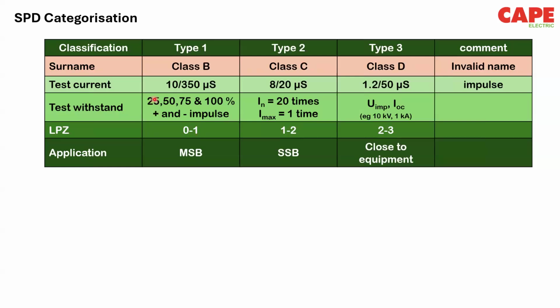Now, how are SPDs categorized? So, as Gopakumar sir said, there are class B, C, and D, the old names. Right now, it is 1, 2, and 3. Type 1 is tested for 10 by 350. Type 2 is tested for 8 by 20 surge current. And type 3 is tested for a 1.2 by 50 voltage impulse. And it's a combination wave where even 8 by 20 is included. So we have three types. Type 1 shall be used in 0 to 1, type 2 shall be used in 1 to 2, and type 3 shall be used in 2 to 3 zone.